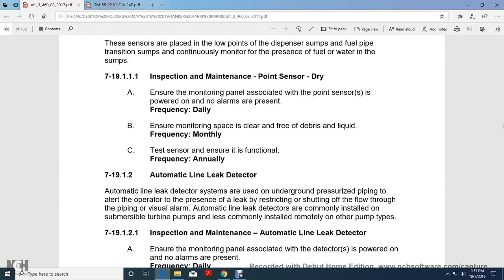Inspection maintenance. Point sensor dry. Ensure the monitoring panel associated with the point sensor is powered on and no alarms are present, daily. Ensure monitoring space is clear and free of debris and liquid, monthly. Test sensor to ensure that it is functioning, annually.